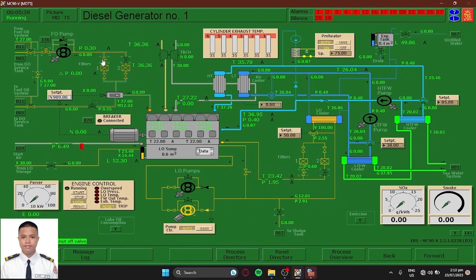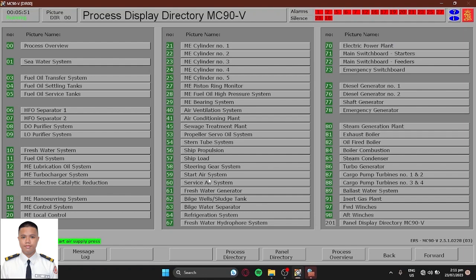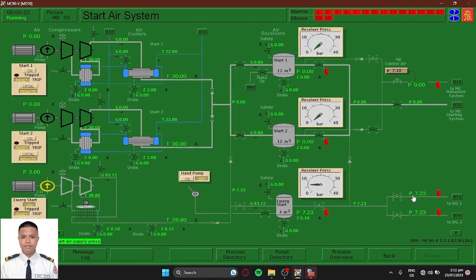Check if you turn on all the valves necessary. So let's check here, check here. You have auto this, and you have the filter and the preheating. So let's just wait for the pressure to go up. We need 11 to 15 pressure. So let's go back to start air. I'm going to turn on this hand pump to help speed up the process here. Let's wait until this pressure reaches 11 bars.